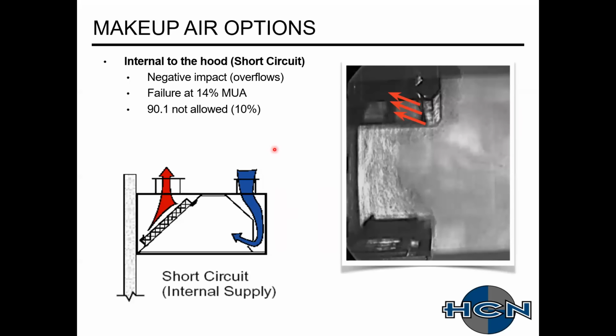Internal comp, one of the poorer performers in this test. Actually, most of these pictures were taken from the PIER test from California, 2003. They did this test in which they tested the effects of makeup air on hoods. Failure at 14%. Actually, ASHRAE 90.1 doesn't allow it to go over 10%. A lot of listed manufacturers are actually not even making internal comp hoods anymore.